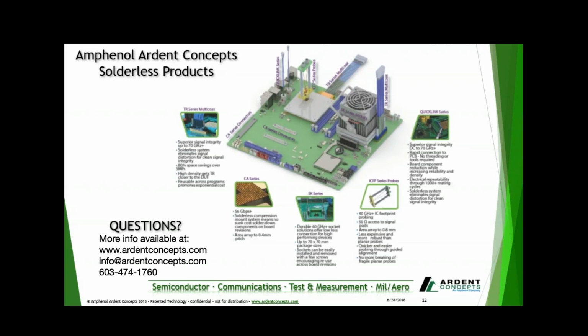What is the max power handling capability of Ardent sockets? Another great question—I did mention we worked at a couple different wattages. The sockets as designed today, Ardent Concepts sockets designed in-house here, are capable of handling 200 to 250 watts. But when a customer requires more power to be run through, that's when we'll use those groups I just mentioned, the Chroma ATEs and Sub-Zero units, to help design a liquid-cooled solution, and we'll work with those outside vendors to do that. As I mentioned, we have a current socket in a customer's lab right now that's running at 350 watts, and they're working with us to jump higher than that as well.